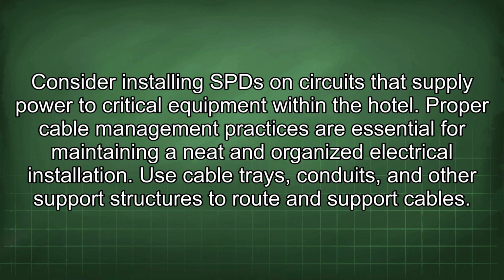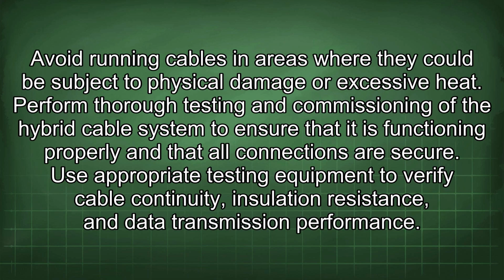Proper cable management practices are essential for maintaining a neat and organized electrical installation. Use cable trays, conduits, and other support structures to route and support cables. Avoid running cables in areas where they could be subject to physical damage or excessive heat. Perform thorough testing and commissioning of the hybrid cable system to ensure that it is functioning properly and that all connections are secure. Use appropriate testing equipment to verify cable continuity, insulation resistance, and data transmission performance.